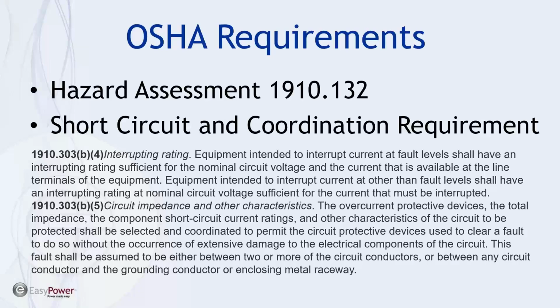Now, let's get back to the question that was on the polls about what about when I do it initially, is that enough? There's nothing in OSHA that says this coordination and short circuit study has to be done periodically or every 5 years. NFPA 70E gives you the guidelines, so there's no guideline in here as to how often this is done. OSHA would go to the NFPA standard as a guideline and with general duty to say it hasn't been done within 5 years. But I don't even know that they would go there. They would just say this is not adequate information because it's been too long since it's been done.